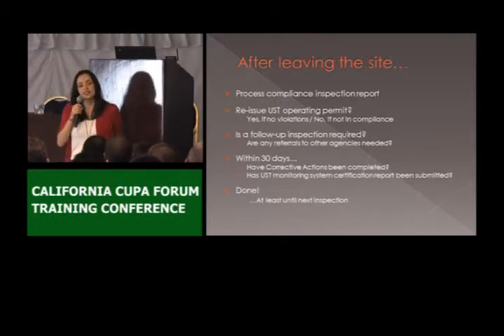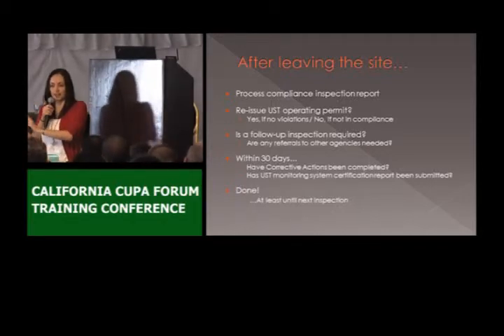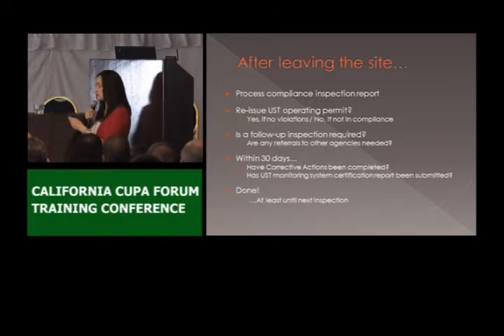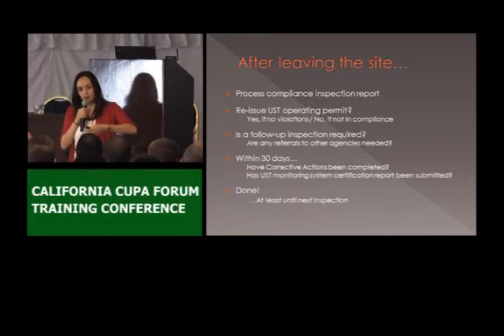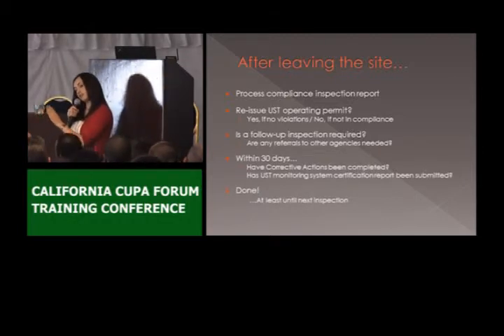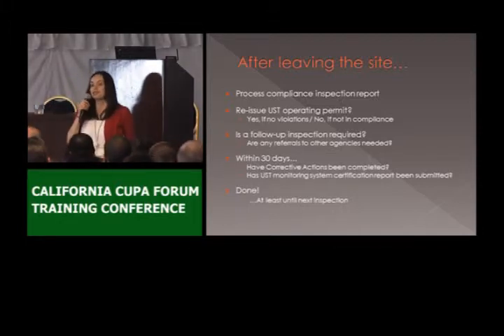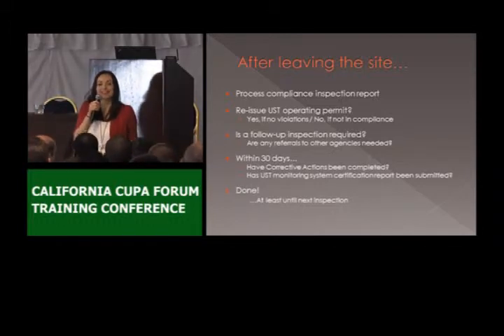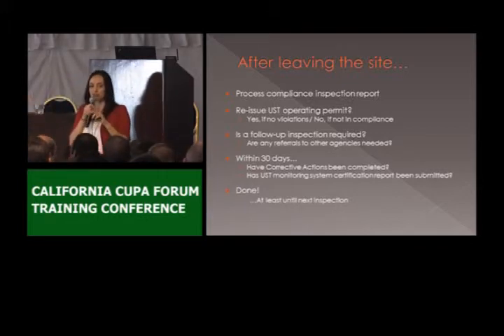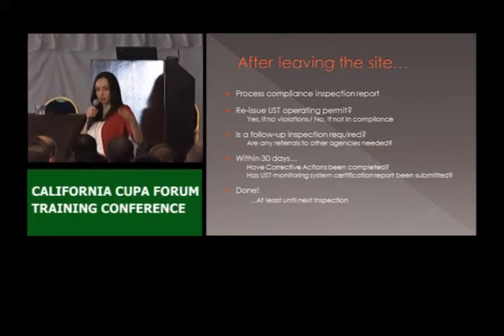Check whether the UST permit is expired or needs to be renewed before your next inspection next year. If it needs renewal and they had no violations, I'm going to issue them a permit again. If there were violations, I'm going to hold on to the permit until I receive evidence that everything was corrected. The permit is good for five years, so we don't have to reissue it every year — just make sure it doesn't expire between your current inspection and the next one.